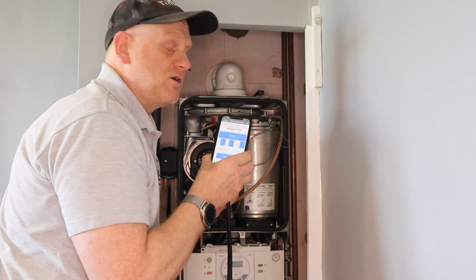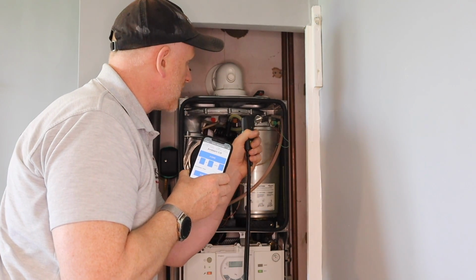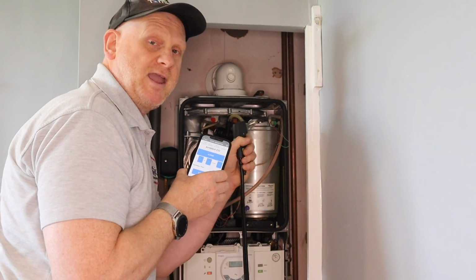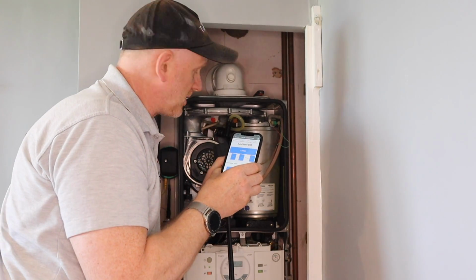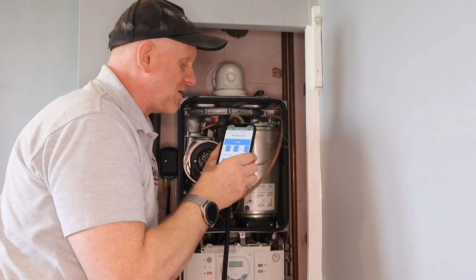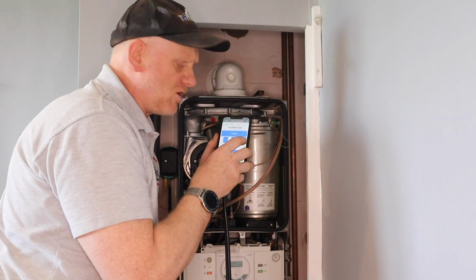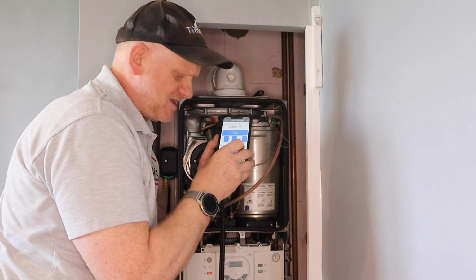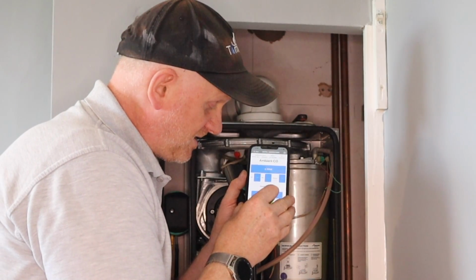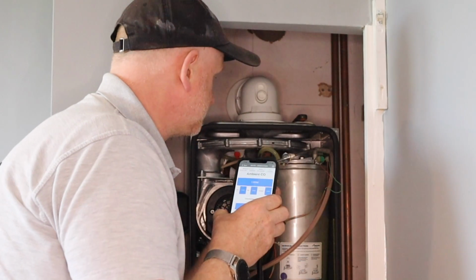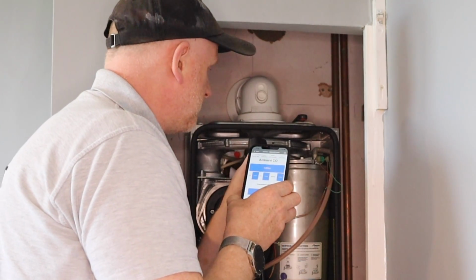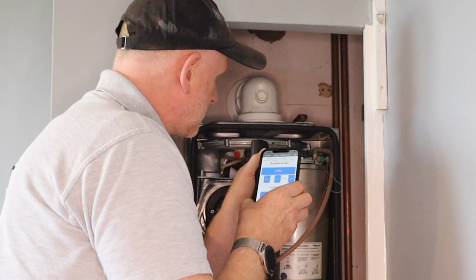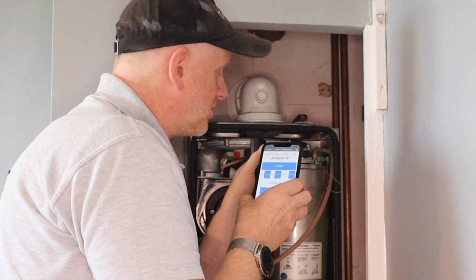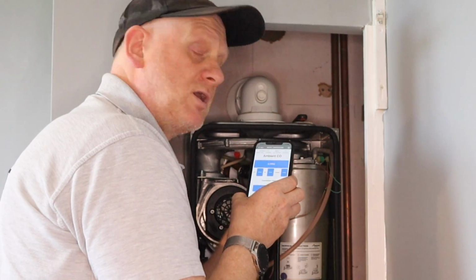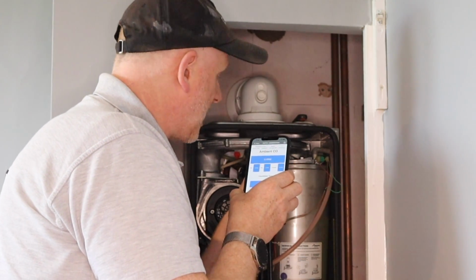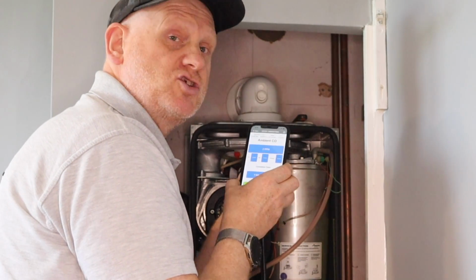So what I've got to do now is sweep around the top here where the gasket has been replaced, making sure I get around the back and making sure I've not got more than 10 parts per million CO. So let's start the test and see what we get. I'm going to start at the middle here and see if we get anything coming round. So I'll get back to you after the 2 minutes and I'll show you the results.